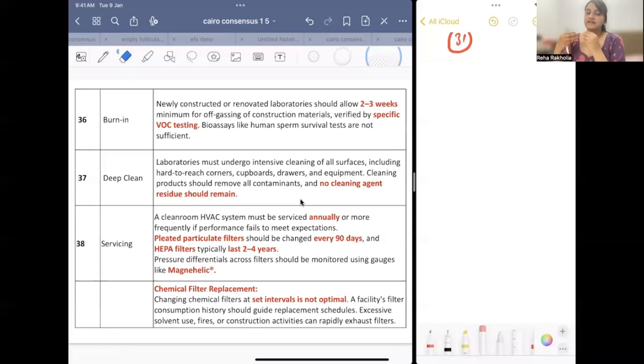If there is fire or if there is construction going on in that area, then the chemical filter will be changed frequently. So we cannot say that this is the optimum time to change the chemical filter. The laboratory's previous performance also we can see to decide when to change. Facility's filter consumption history should guide the chemical filter replacement schedule.